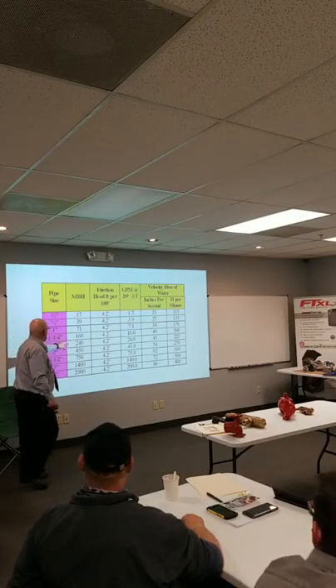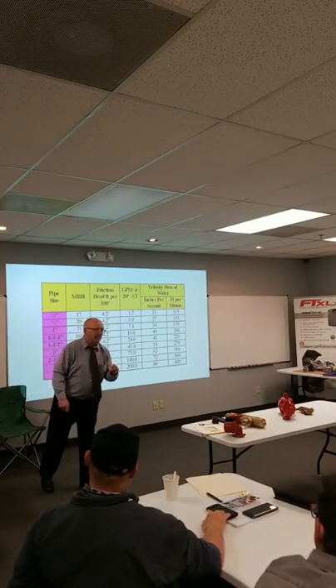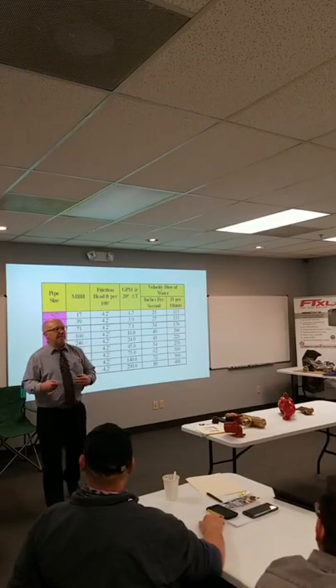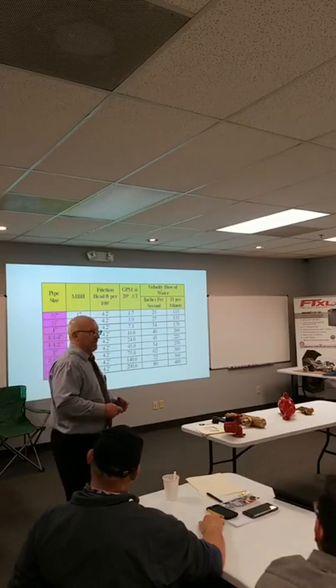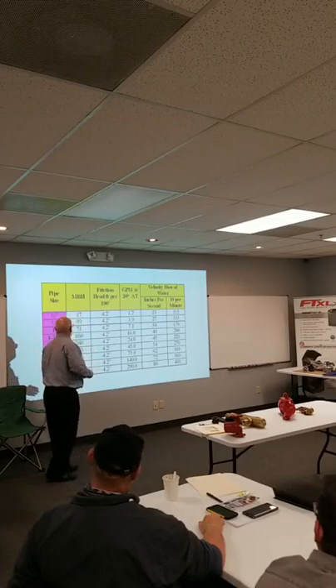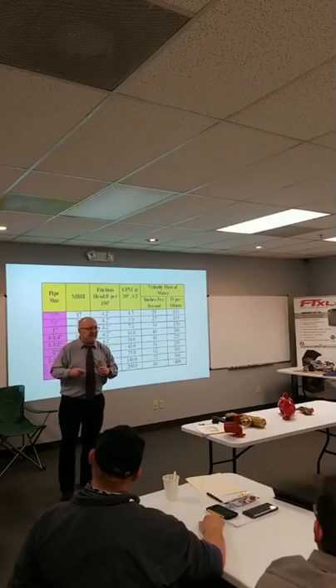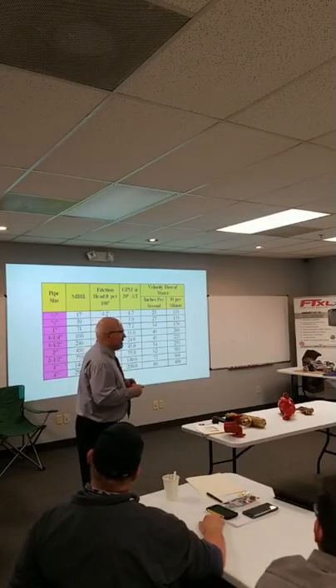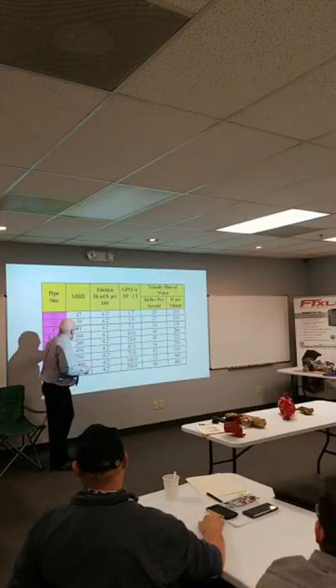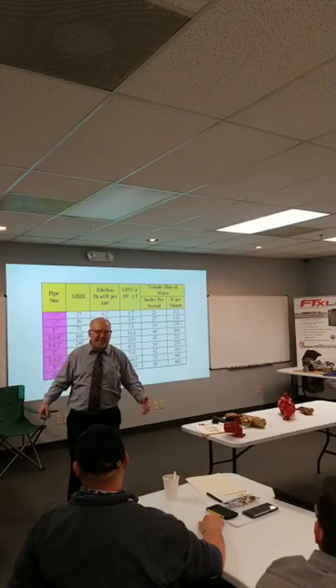So if you have 200,000 BTUs that you want to deliver, okay, and you have inch and a quarter pipe, are you going to be able to get 200,000 BTUs out of it? No. Page 36. No. Page 36. Thank you. Okay? So it's very important if you do service, you need to almost understand these numbers. If I'm trying to deliver a zone and I've got a 2-inch pipe going to that zone and I've got 600,000 BTUs connected to it, I'm not going to get it.